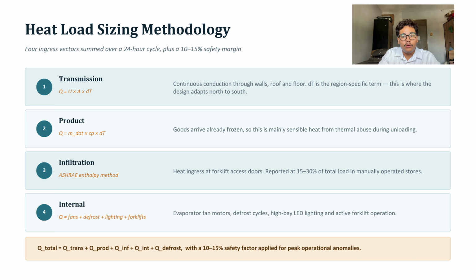And finally, we have the internal load, which consists of the evaporator fan motor, defrost cycle, high bay LED lighting, and active forklift operation. So we sum these variables and apply around a 10 to 15% safety factor for peak operational anomalies. The total is what our system is sized to handle.